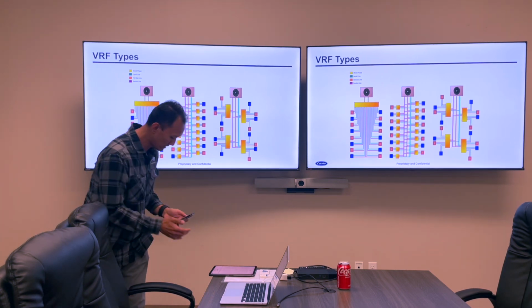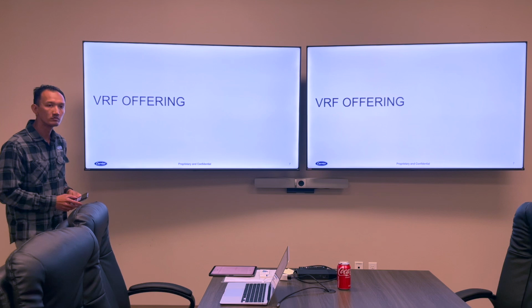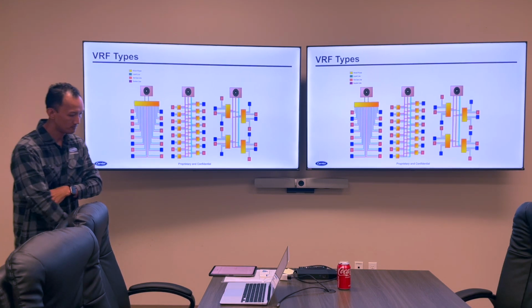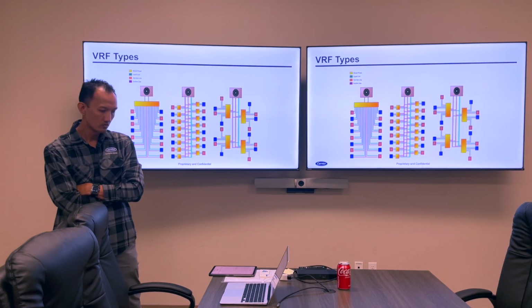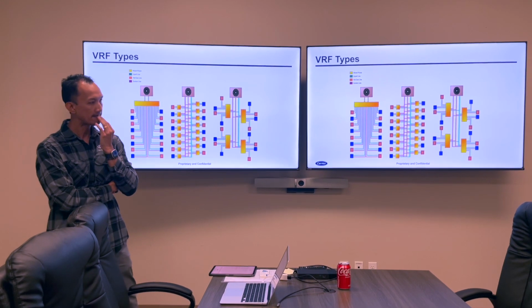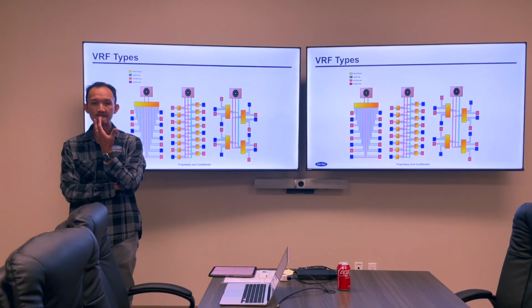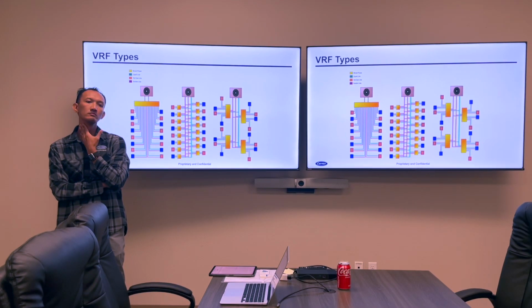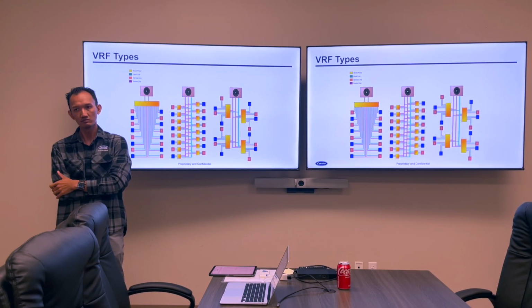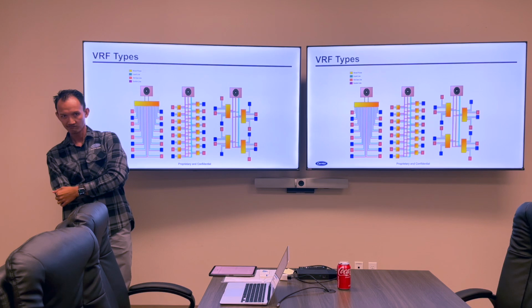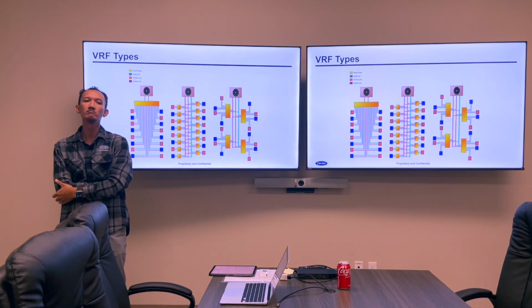No questions, right? All good? Just something real quick that I would like to jump in on too. Especially if you don't know where to put flow selector boxes, or you need rough refrigerant charges. If you just send me floor plans, tell me where the fan coils are, or where the condenser is, I can run the pipe lengths for you.